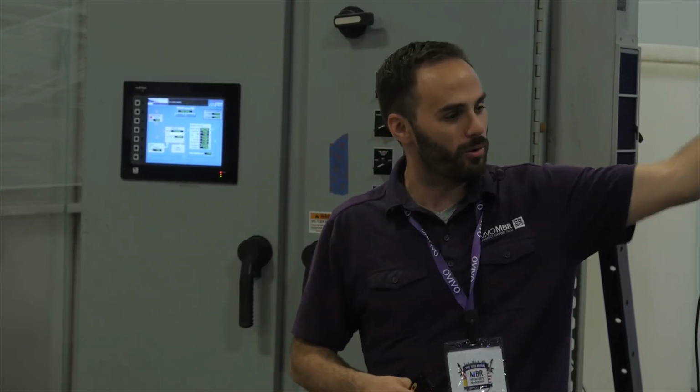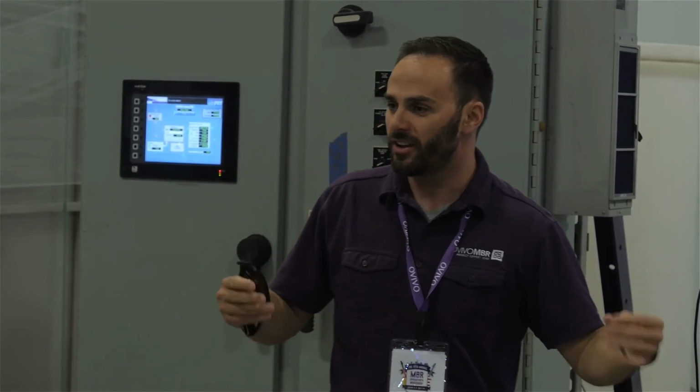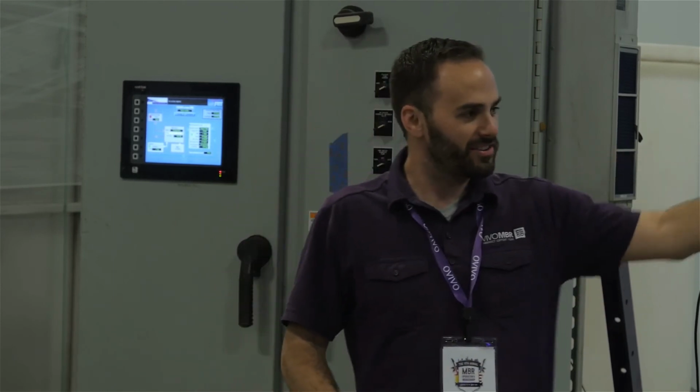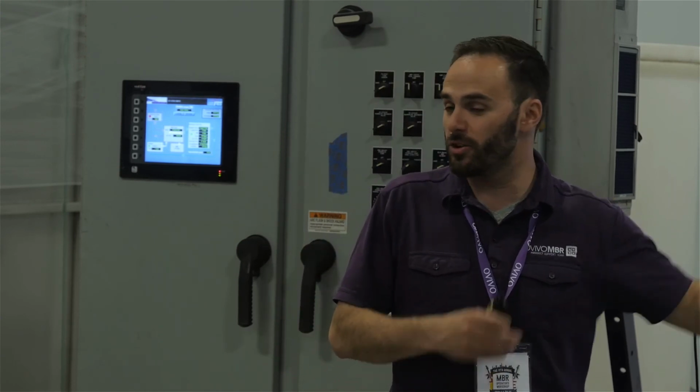If you want to come up over the wall like that and back down, when you go into an intermittent and the flow stops, that dissolved oxygen will come out of solution over time and start to build up, and it'll raise up to the high point like we have up here, and you can see it in that pipe. So it's going to get there, it'll show up. It doesn't matter if your piping is tight or not. Obviously if it's not, you're going to have a bigger problem. But that air will build up there, and you will see the effects on this equipment if we don't have a way to get that air out of the system. So I do want to point that out.